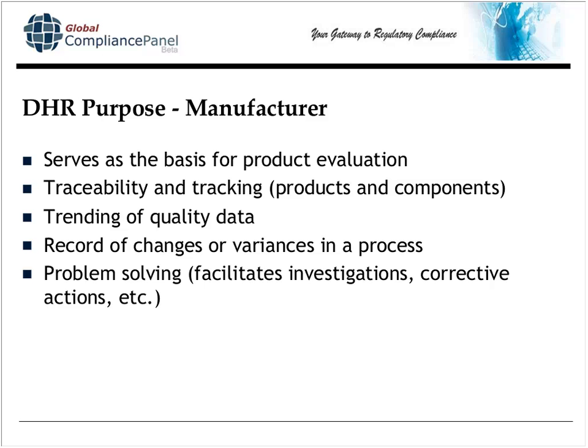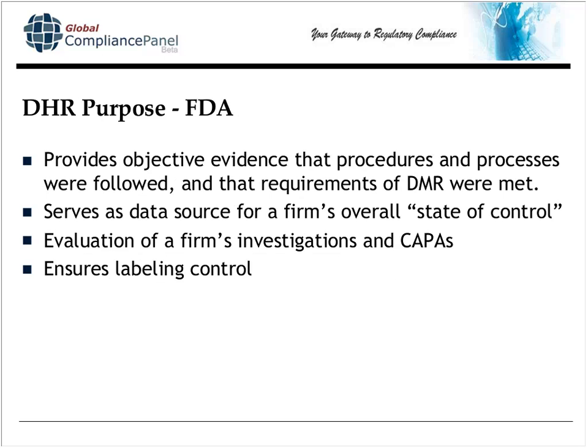The DHR also lets you do problem solving. When it comes to investigations or corrective actions, all the documented information assists you in performing investigations for complaints. From the agency's perspective, the DHR shows that you followed your own procedures and your product is in compliance with the DMR. The agency likes to use the term 'state of control,' and the DHR is a great data source for them to qualify that. The FDA also likes to see you use your DHRs and reference them when investigating in-process nonconformances and field-reported nonconformances, and they like to see that information fed into your CAPA system. Label control is also documented in your DHR, enabling you to control labels better.